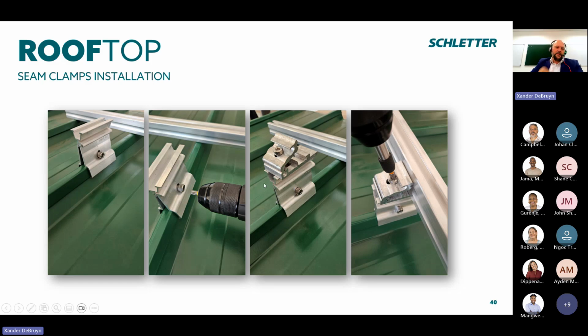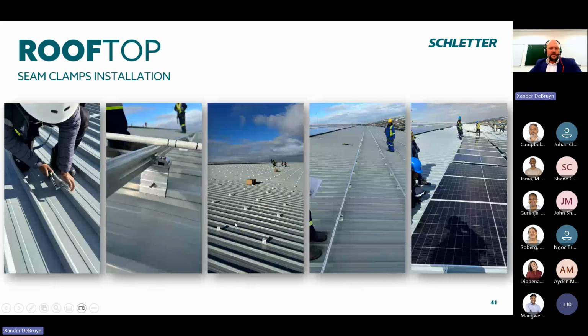Okay, so what that looks like, basically, you place your seam clamp onto that mountable seam of the roof. One tool required, drill using your Torx T40, just like the module clamps, to fasten that to the roof sheet. If you're doing a rail system, cross connector comes on, place the rail onto the cross connector, fasten again with Torx T40. So one tool is required to fasten the module clamp, the same tool for the cross connector, and the same tool for the seam clamp. So looking at that on a larger scale installation, fasten the seam clamp.